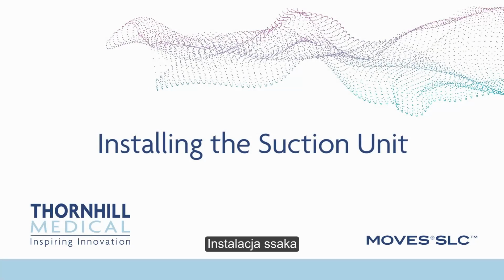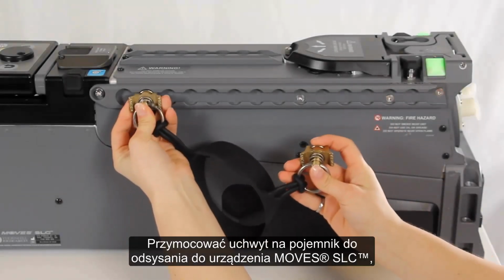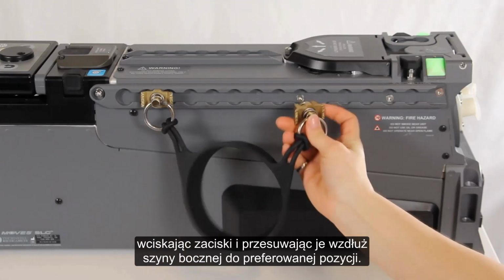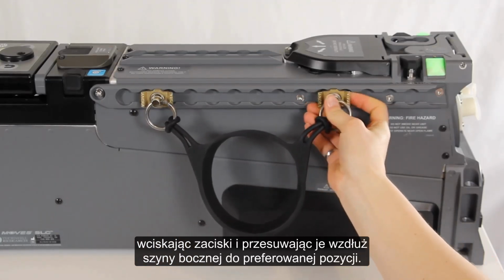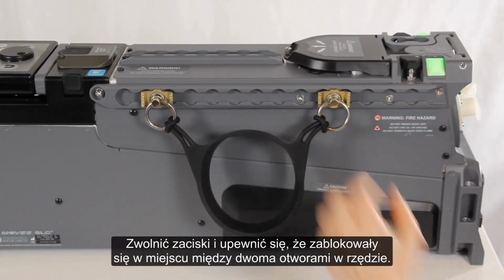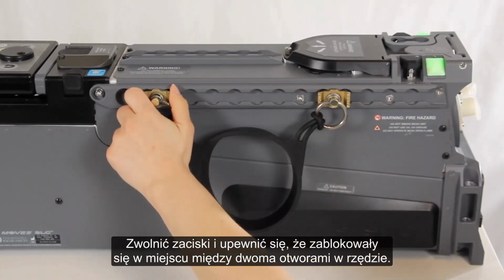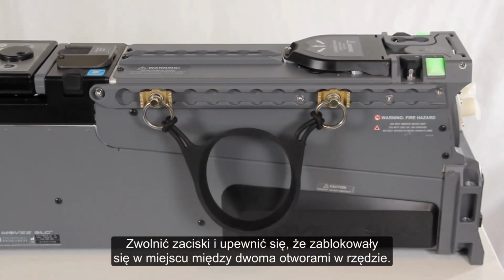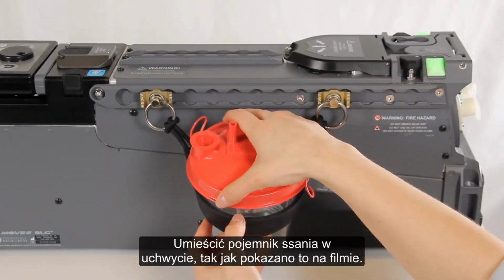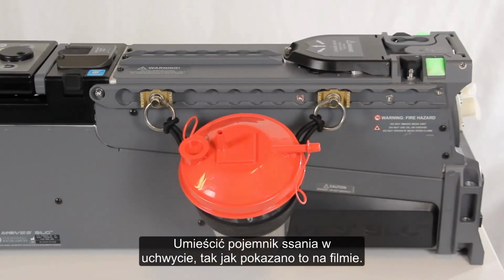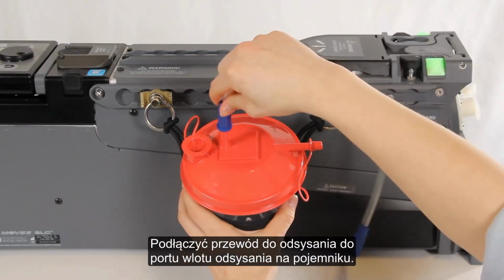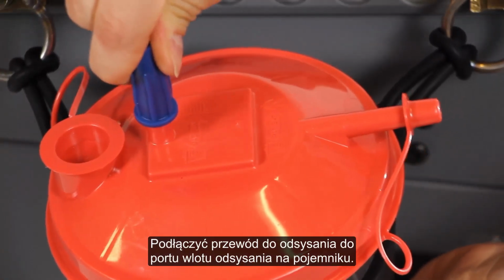Installing the suction unit. Attach the suction bucket holder to the Moves SLC unit by depressing the clips and sliding them along the side rail into the preferred position. Release the clips and ensure that they lock into place between any two holes in the row. Insert the suction canister into the holder as shown. Connect the suction hose to the suction inlet port of the suction canister.